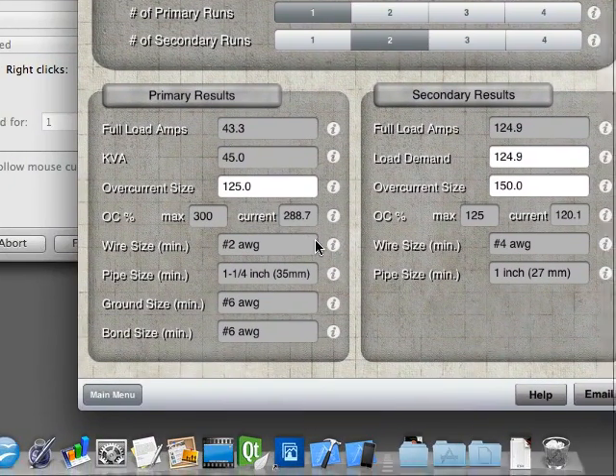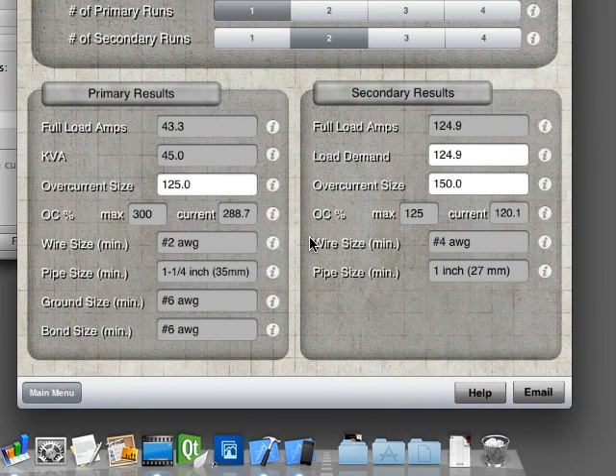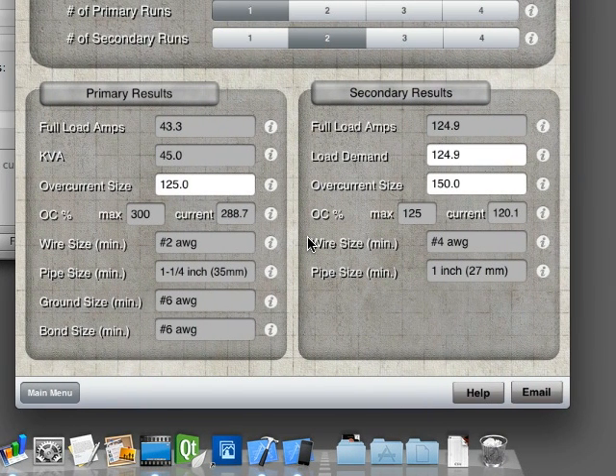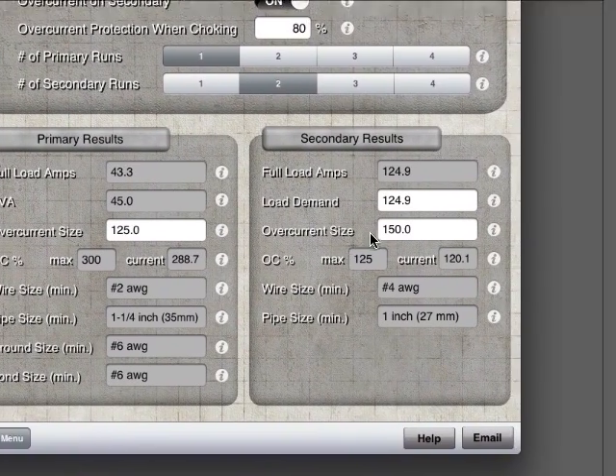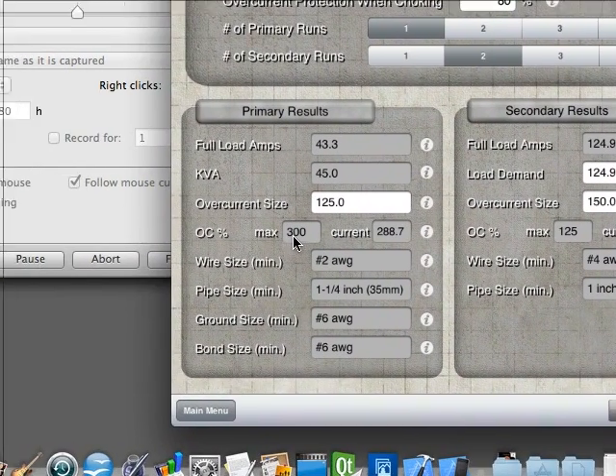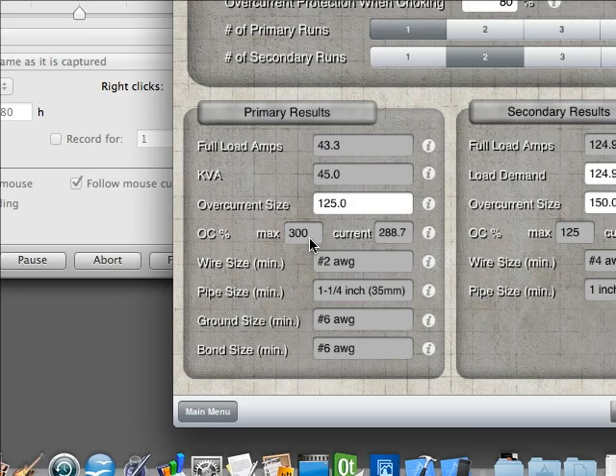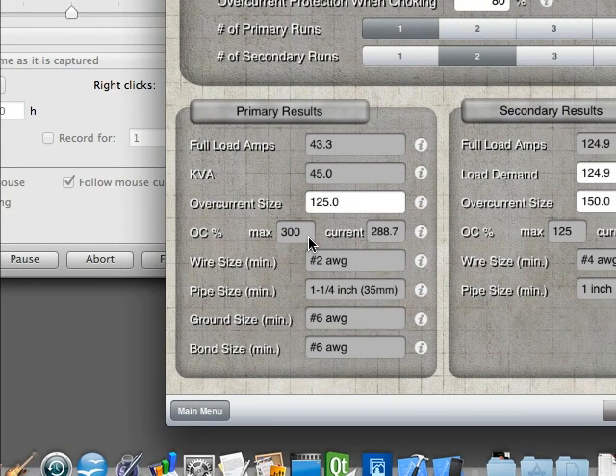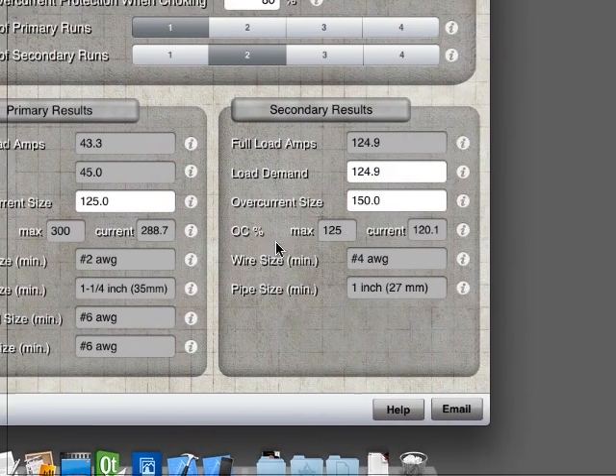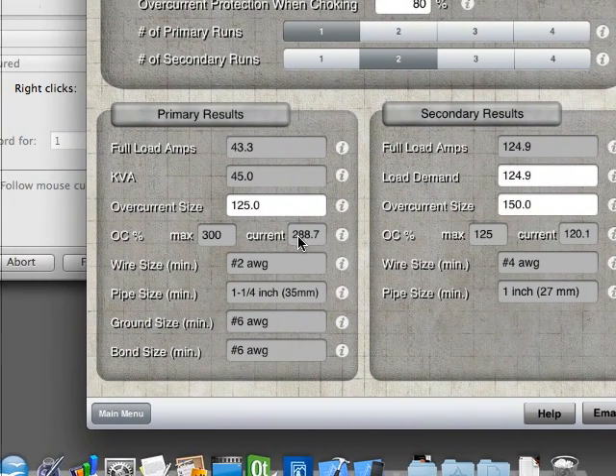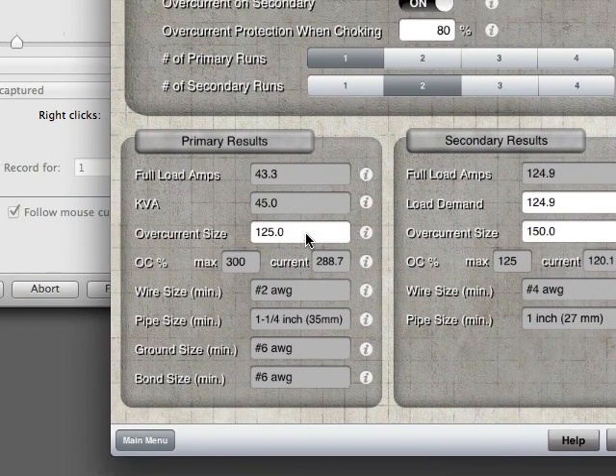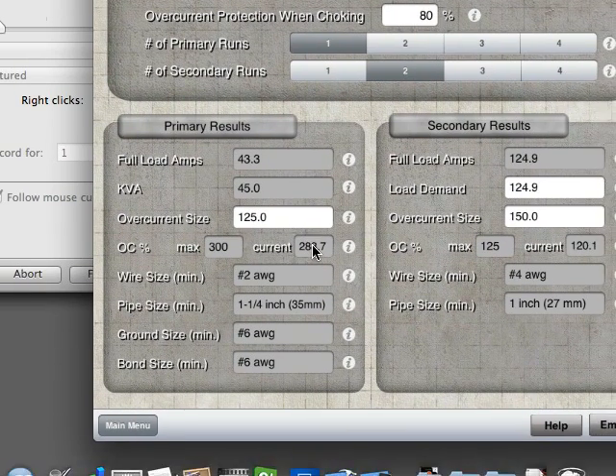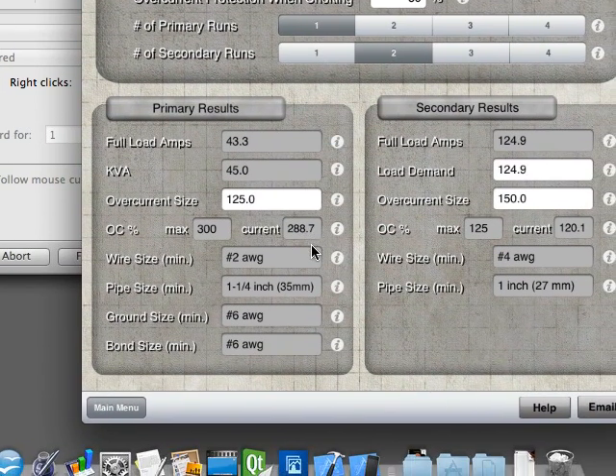It will give you your full load amps, both primary and secondary, your KVA, your overcurrent size, which by default sets to its maximum size. And it also gives your overcurrent percentage, so your maximum percentage, which is 300% on your primary right now because we have secondary protection. And it will give the actual percentage, so we're set to a common fuse size here of 125, which gives us a 288%.